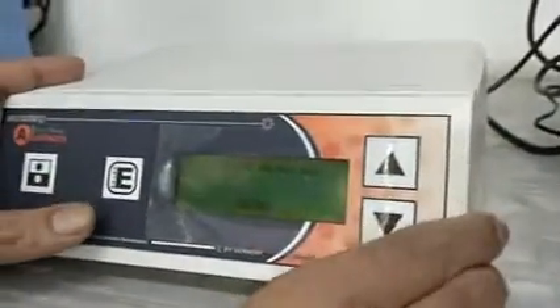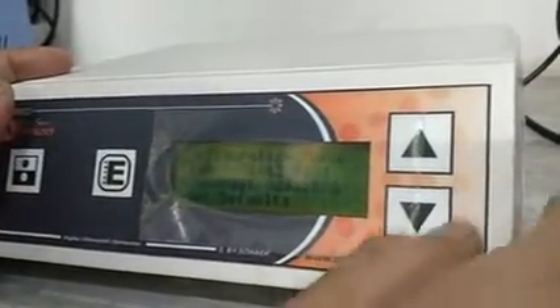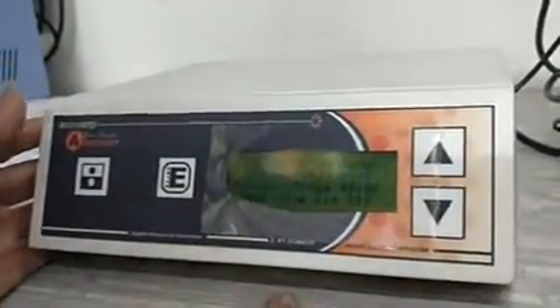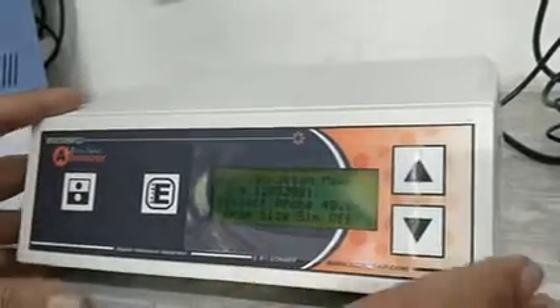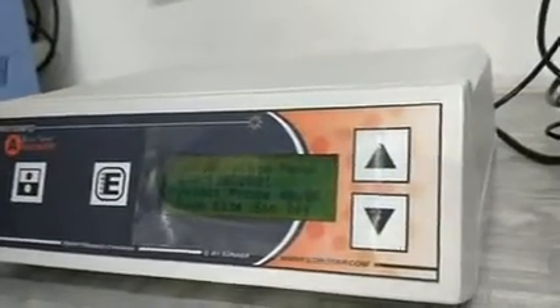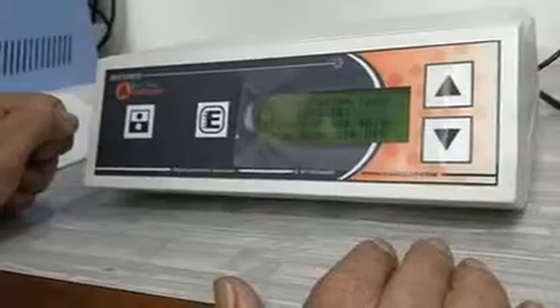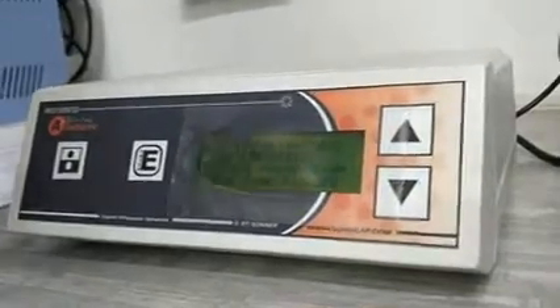Let us start with the parameters of the atomizer generator. If you want to check the parameters, you go to this enter key. Normally this comes first: the serial number, and then select probe 40 kilohertz. This generator, the same generator, can take 20 kilohertz, 40 kilohertz, 60 kilohertz, and 130 kilohertz frequency nozzles. So if you have different nozzles of different frequency, you can run those too. If you want to change it, press enter.